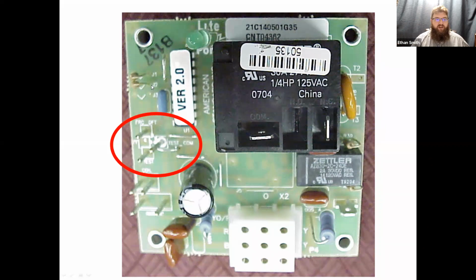Oh, I know what I forgot to add. So remember, guys, there's these jumpers up here. Refer to the manufacturer's documentation. If you've got that high humidity environment, you need to raise that termination temperature. You're going to clip 1 or 2 of these jumpers depending on what you need to get it into a medium or a high temperature.